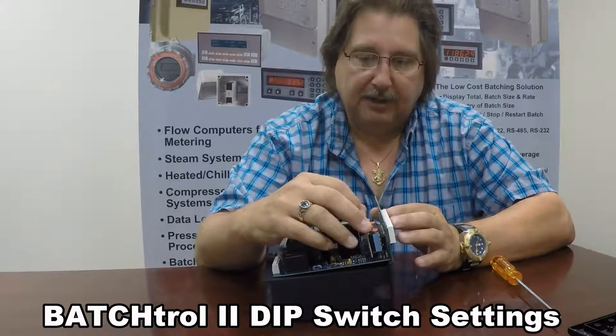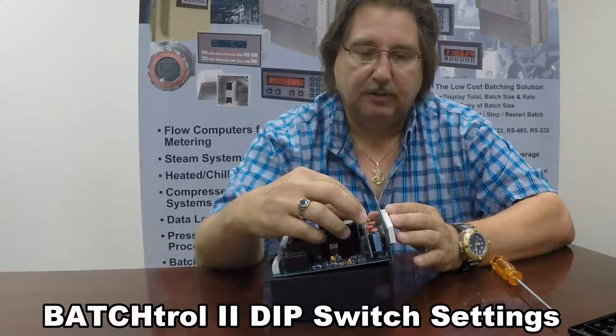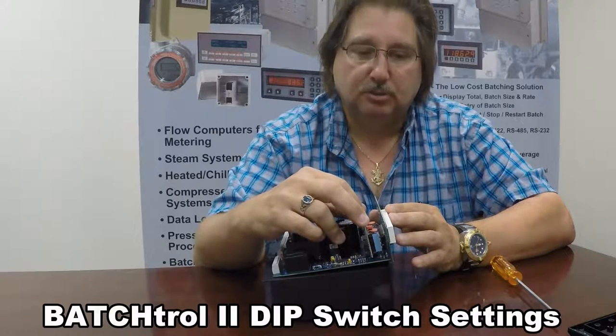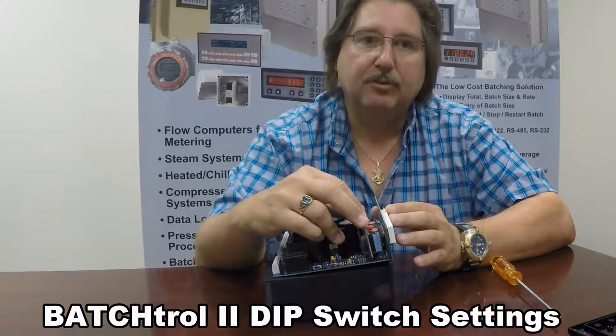Switches one and two allow you to change the frequency at which the BATCHtrol will accept the pulse. You can do 40 hertz, which is switch one and two on; 400 hertz, which is switch one on and switch two off; or 20 kilohertz, which is switch one and two off.